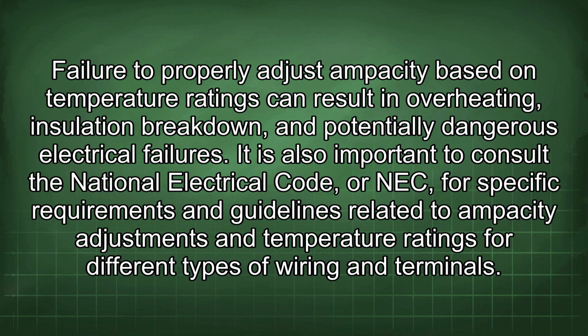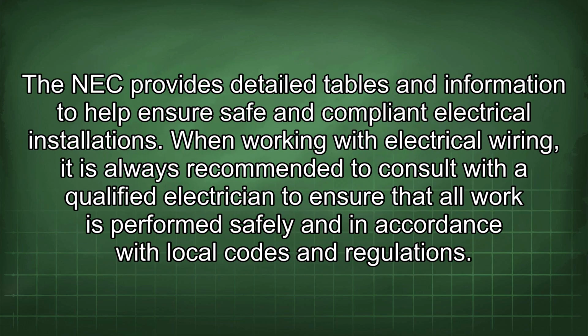Failure to properly adjust ampacity based on temperature ratings can result in overheating, insulation breakdown, and potentially dangerous electrical failures. It is also important to consult the National Electrical Code, or NEC, for specific requirements and guidelines related to ampacity adjustments and temperature ratings for different types of wiring and terminals. The NEC provides detailed tables and information to help ensure safe and compliant electrical installations.